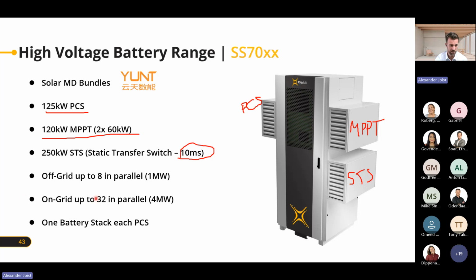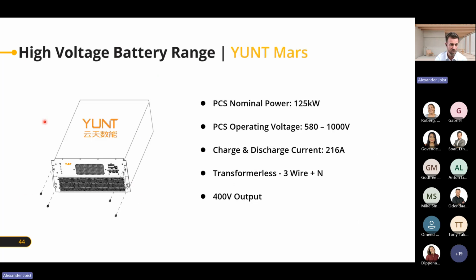If we now go to the next slide, the YUNT PCS, it's a rack mounted PCS. So what we do is we put a housing around it, so it's going to be IP65 rated. Because this is only IP21, so only for indoor operation, but we're going to put a housing around it and filters and all of that, so that no dust and water can come in. And we make this product IP65 and connect it outside to the solution. And then you have a 125 kilowatt PCS. It's transformerless, but it has 3 wires plus N plus PE, of course. And 400 volt output. So you don't need a transformer for this.